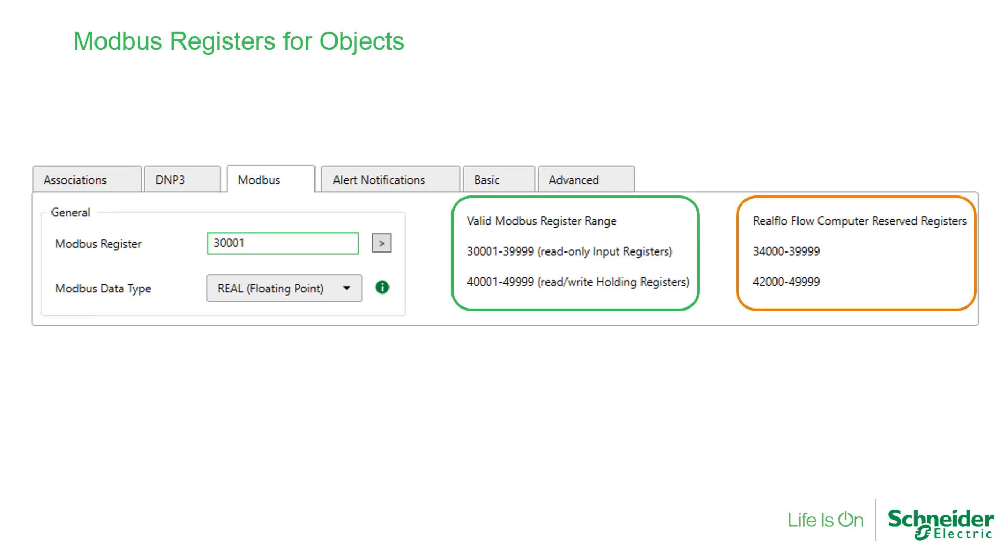Currently, all Modbus addresses for flow runs 1 to 10 are reserved in the SCADA pack when the flow computer is enabled, even if all flow runs are not configured.